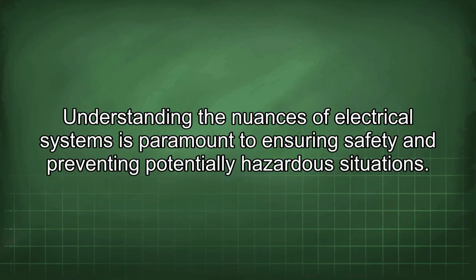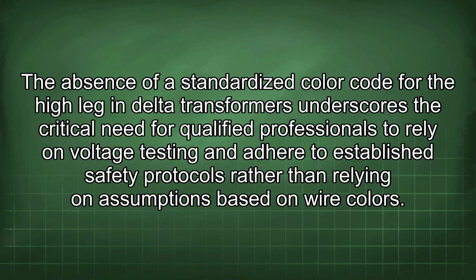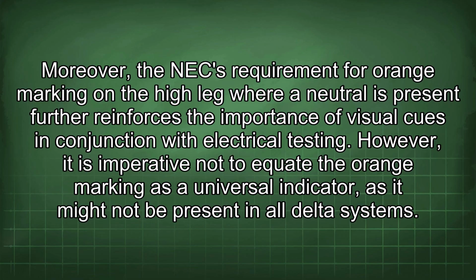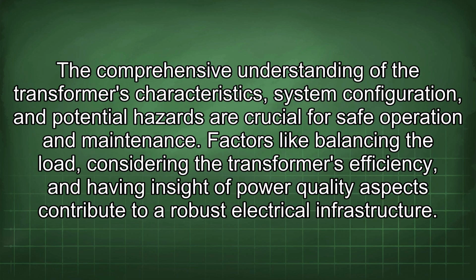Understanding the nuances of electrical systems is paramount to ensuring safety and preventing potentially hazardous situations. The absence of a standardized color code for the high leg in delta transformers underscores the critical need for qualified professionals to rely on voltage testing and adhere to established safety protocols rather than relying on assumptions based on wire colors. Moreover, the NEC requirement for orange marking on the high leg where a neutral is present further reinforces the importance of visual cues in conjunction with electrical testing. However, it is imperative not to equate the orange marker as a universal indicator, as it might not be present in all delta systems.